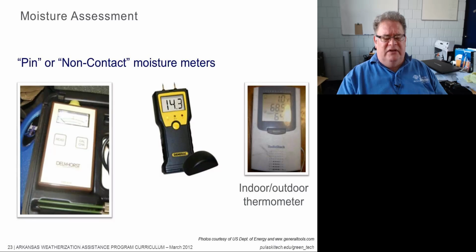The 2 that we have on the left are pin and non-contact. The one we have on the right is really an indoor-outdoor thermometer with a relative humidity gauge built into it, and those are good for reading relative humidity within the house to know whether or not we're doing a good job, such as the air conditioning. If it's cool in the house but the humidity is high, this would show that we have high humidity and give us a number to work with.